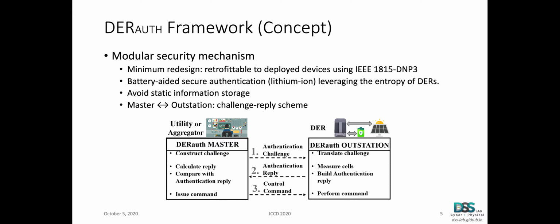It requires DER outstation devices to be authenticated before control commands can be issued from the DNP3 master. The authentication process leverages the intrinsic characteristics of the battery energy storage system lithium-ion battery cells to generate entropy, specifically cell voltage and state of charge measurements and their inherent randomness caused by the unique lithium-ion physical properties due to their manufacturing process. To summarize, we developed and ported a battery storage-based authentication scheme into the DNP3 protocol stack.